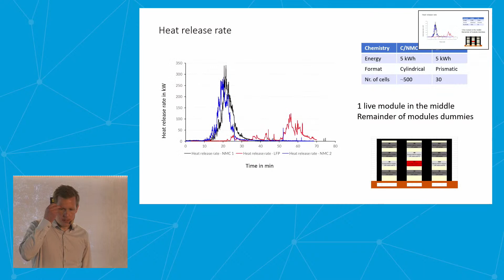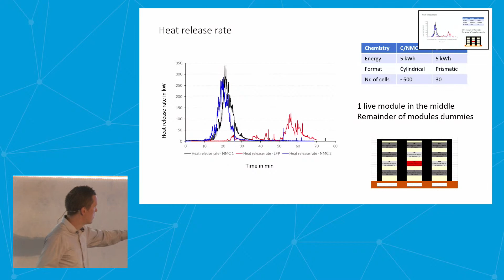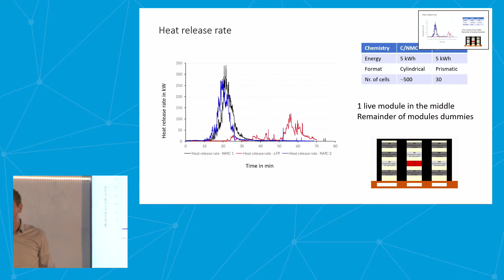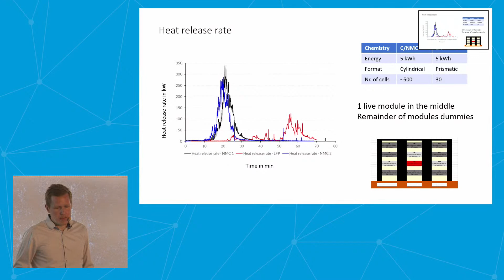We tested 2 different modules. So we had a test setup here with the red module as the live module, and then dummy modules surrounding it. And it was 2 different chemistries, the same amount of energy, but different formats and size of cells. And we could conclude that the repeatability was good between these 2 tests with the same type of module. This is the heat release rate. But you could also see that there's a large difference between the different types of battery modules here, with much lower heat release rate for the red curve here. Good enough. We moved on to suppression.